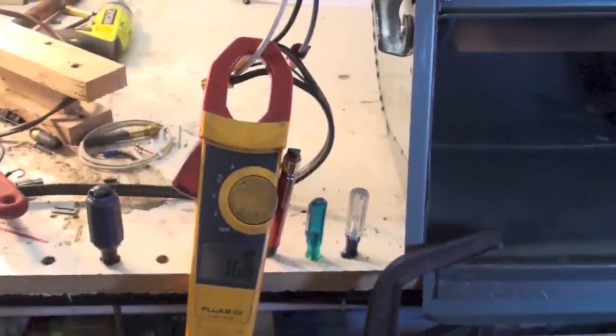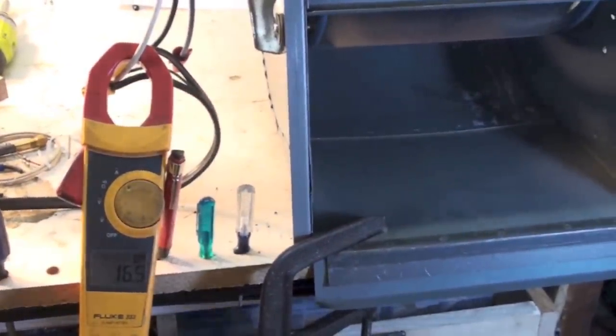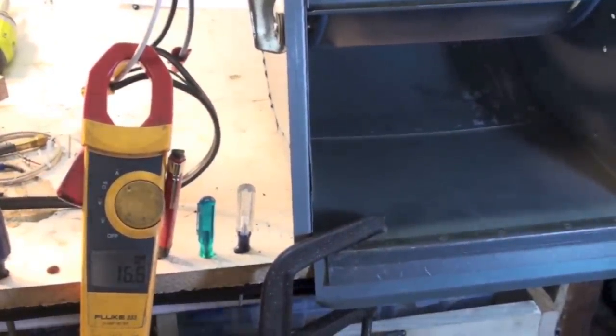Okay, this is important because this fan motor is rated for 9.1 amps, so it's drawing pretty close to twice the amp draw.